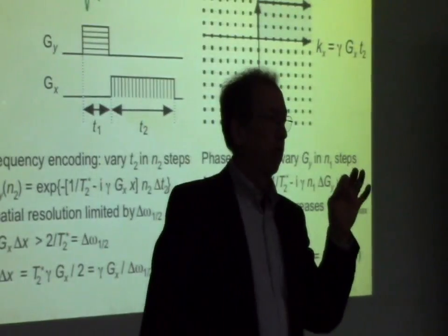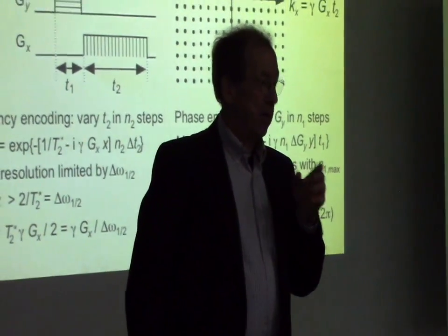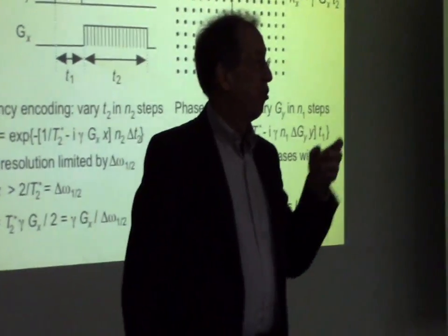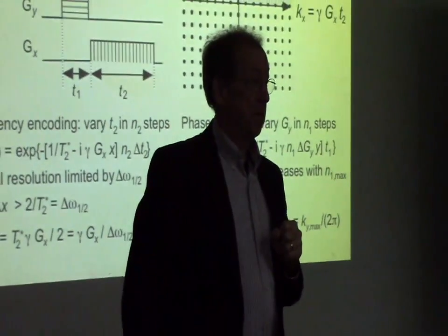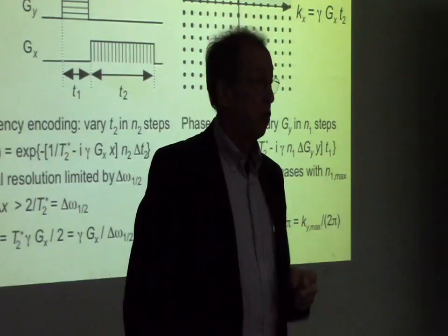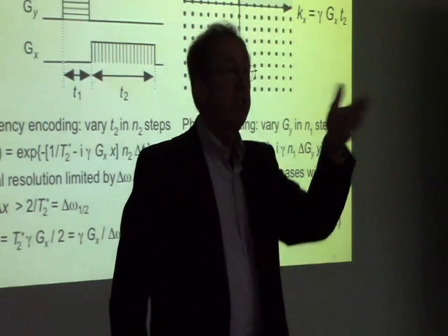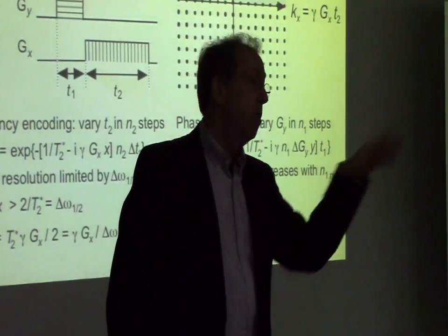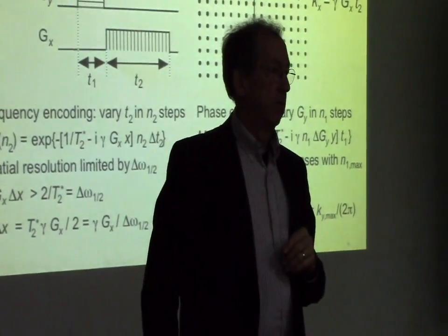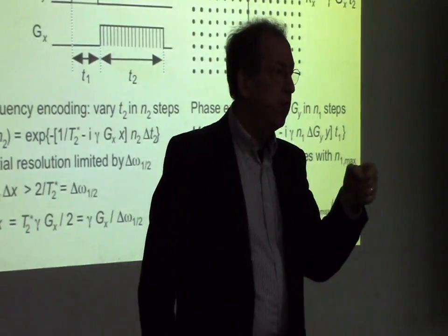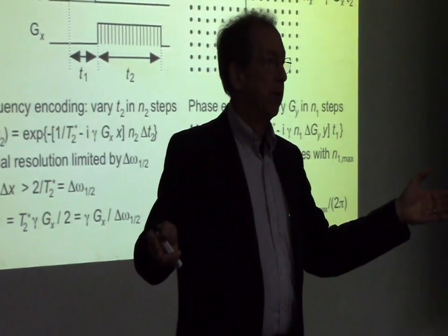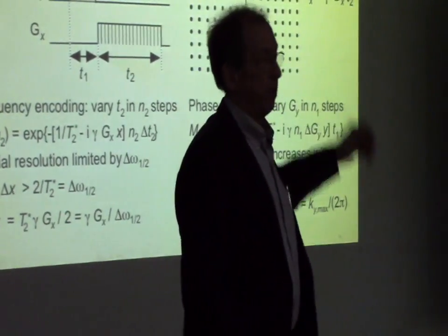F is usually taken, one usually designs spectrometers so that F is 0. But what hasn't been done yet is to make use of F. So if you are clever, you say, I want to build a simple spectrometer, or let's say I only want to measure velocity, no imaging. You can use F and build a very simple instrument that allows you to build an NMR flow meter, for example. And then one could use F.